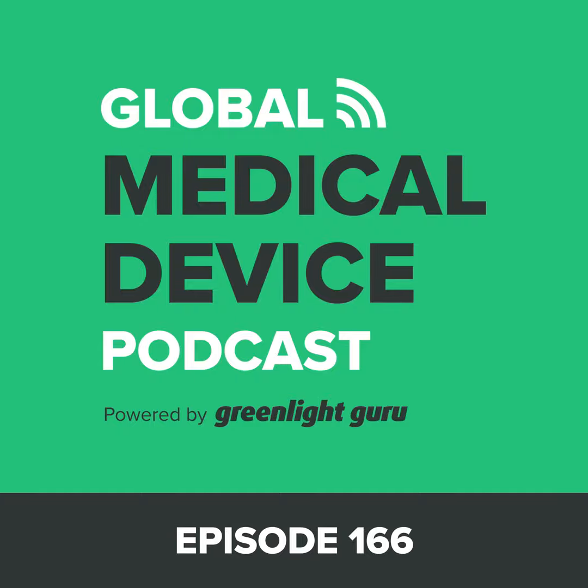So here's my next suggestion or concern from the guidance. Another thing that FDA asks for is a history of adverse events that have been experienced from this material. Remember, we're talking skin contact applications here, John. So we're talking about things like redness and swelling and irritation and sensitization and allergic or other immune responses and so on. They're asking specifically for these adverse events being reported in clinical studies.